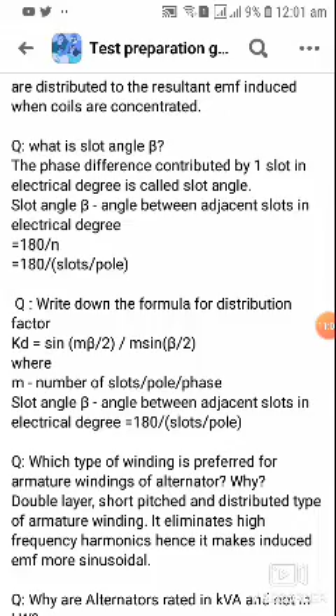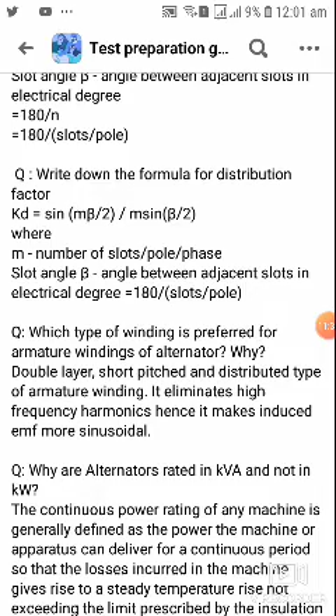Question number 24. Write down the formula for distribution factor. Kd is equal to sine of m beta by 2 divided by m sine of beta by 2, where m is the number of slots per pole per phase. Slot angle beta, the angle between adjacent slots, is in electrical degrees 180 degrees divided by slots per pole.